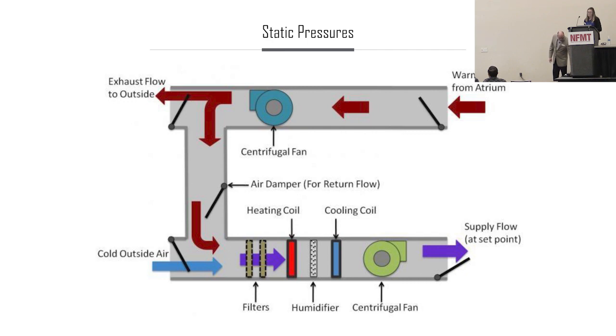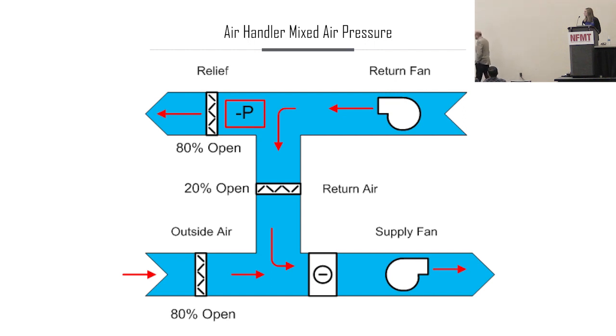All right, so one of the other things that we use as a diagnostic tool is we go about measuring the static pressures throughout the system. And what we're looking for is the unexpected pressure changes given that particular point in the system. So it's just a very generic graphic here, but one of the cases that we can run into, and in fact we did at a sporting facility, what we're expecting to see is good positive pressure there at the relief. Or this is the system we want. Yes, we want to be seeing positive pressure there in the relief, a little bit of negative pressure there in the mixing box.